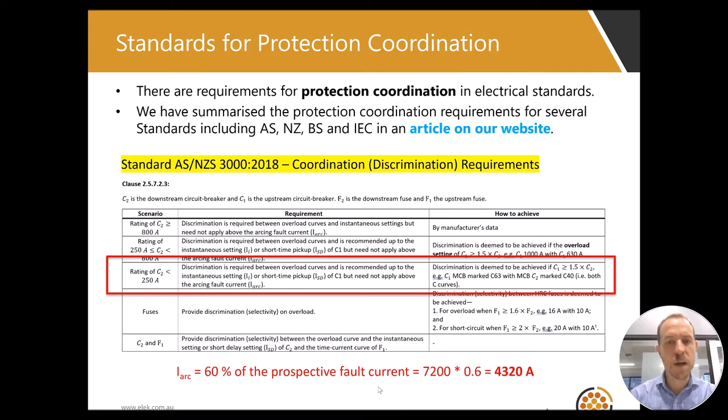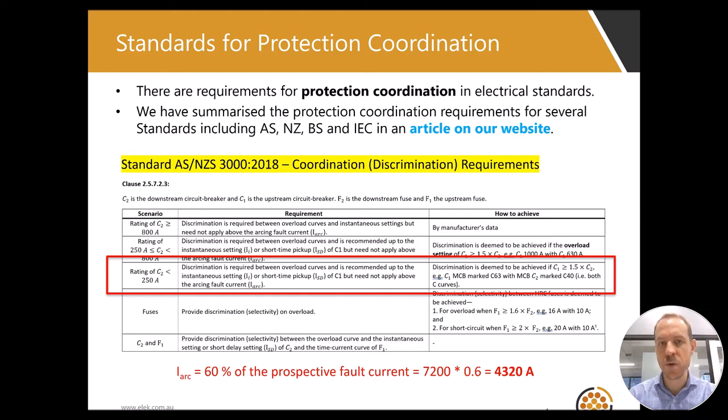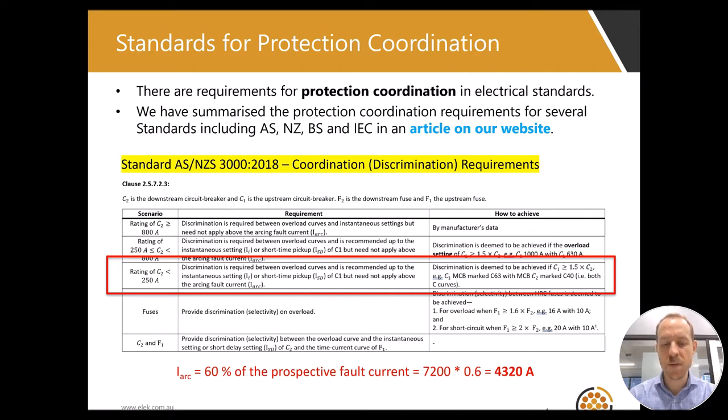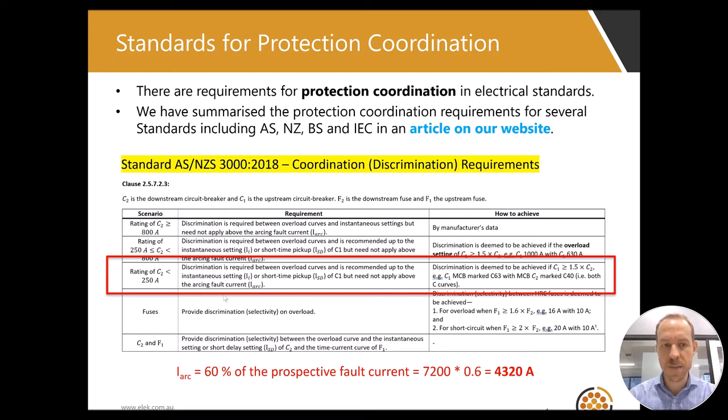There are several electrical standards which include requirements for protection coordination. The standard AS/NZS 3000 is quite prescriptive and provides some guidance, but only up to 800 amps. The table from the standard is shown here in the slide.